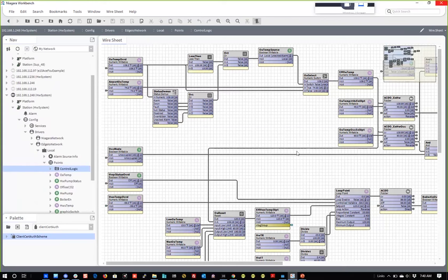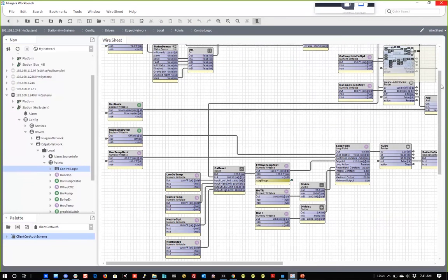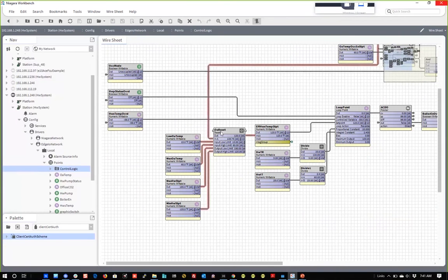So now in order to use this with the ACE, with the application control engine, I have to reprogram it. There's no conversion. And you have to use the components that are available in the ACE catalog. It's very similar to kit control, but there are going to be some areas that are different. For whatever reason, they covered most of the components, but like this reset block doesn't exist in the catalog. So I had to actually recreate that with standard math blocks to do the reset. That was one area that you'll see that's different.